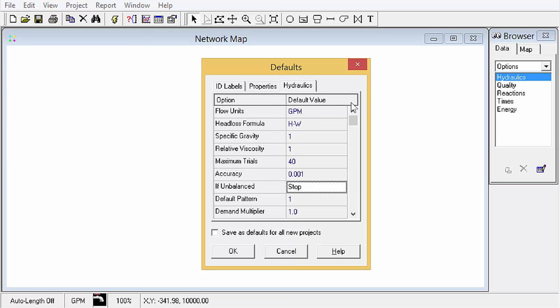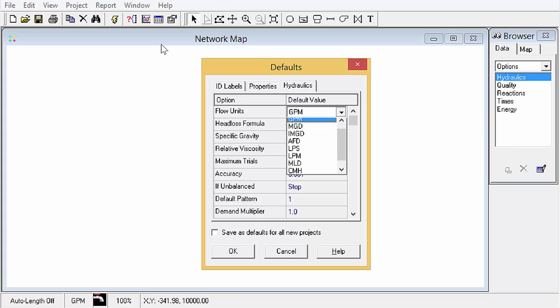As far as hydraulics goes, you've got flow units. This is a very important one to set up in the beginning. This determines whether the model uses SI units or English standard units. So any flow unit that you choose here that is English will mean that everything else is in English units such as your length, diameter, etc.